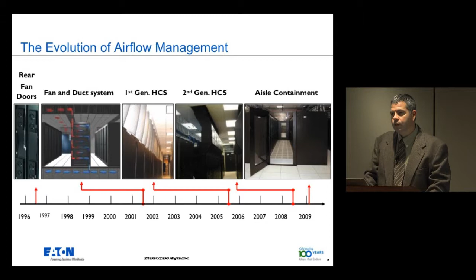So we wanted to show four temperatures that you want to keep in mind that will indicate to you whether or not you have chaos cooling present in your data center. Really it's four temperatures, but two deltas that you want to measure. The first is the difference between the air coming out of the bottom of the CRAC unit, if that's what you have, or whatever cold air supply you're using, and the air going into the server. If those two temperatures are different, there are losses in how the cold air is being supplied to the servers. And likewise, the air temperature in the back of the rack compared to the temperature that the CRAC unit sees. You want them to be as close as possible to the same. Otherwise, there's probably air mixing going on in the room.